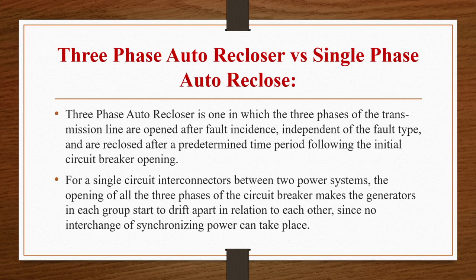So three-phase auto reclosure is one in which the three phases of the transmission line are opened after fault incidence, independent of the fault type, and are reclosed after a predetermined time period following the initial circuit breaker opening. For a single circuit interconnector between two power systems, opening of all three phases of the circuit breaker makes the generators in each group start to drift apart in relation to each other, since no interchange of synchronizing power can take place.